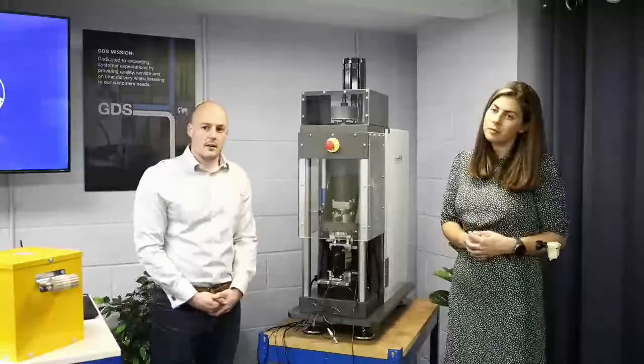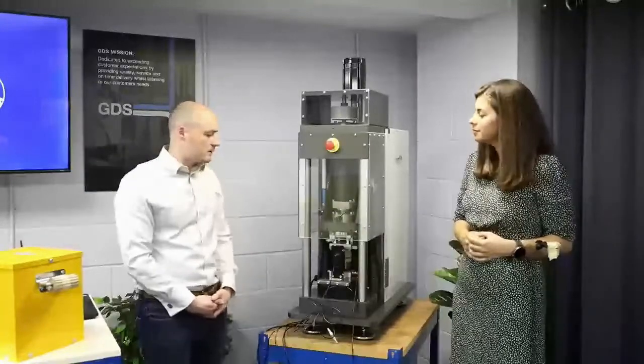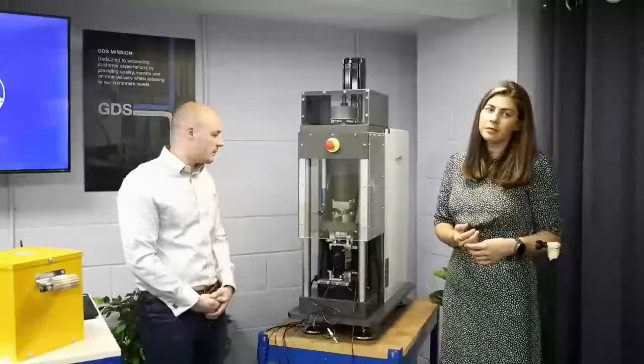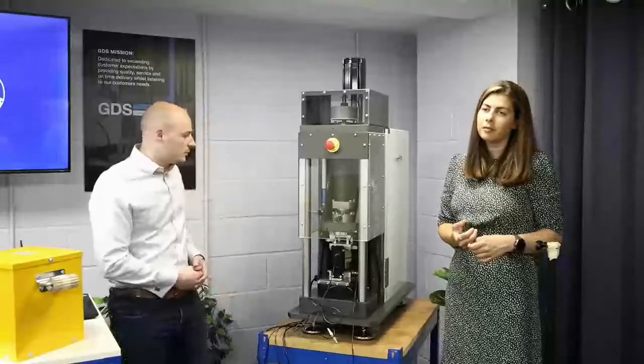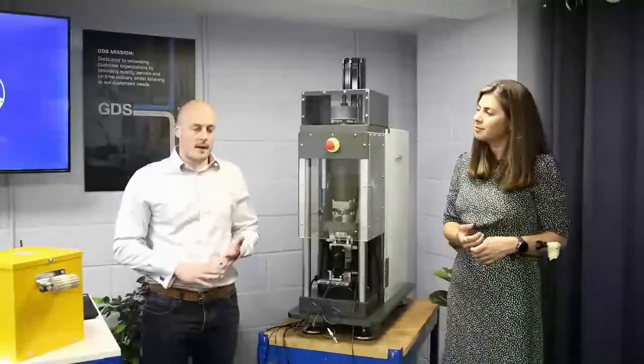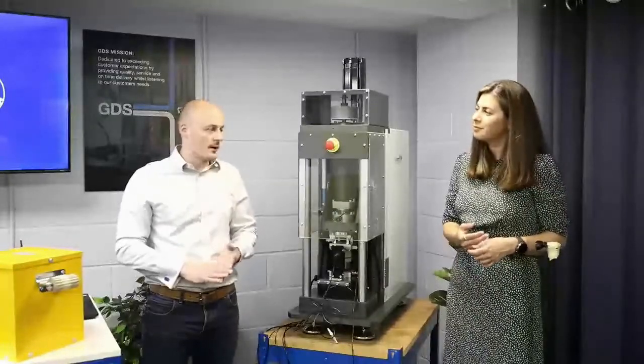So this is a dual-axis electromechanical system rather than a pneumatic or hydraulic system you may get from other suppliers. Pneumatic systems inherently are restricted to sine waves. That's just because of the control problems with pneumatic systems. This machine will do sine, triangle and square waves, and custom waveforms, up to 1,000 points as a custom waveform. Our standard configuration has 2 vertical displacement measurements.